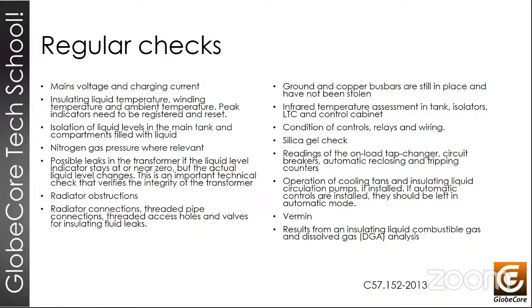Sure. So, all right. As we'll see, there is a more or less typical process or configuration for transformer maintenance. What we do first, we analyze the oil, and we also conduct electrical tests. This is usually done at the same time as electrical testing and oil analysis. We do all this simultaneously, and then we're going to inspect the transformer externally. And this alone will give us a lot of information about our situation.